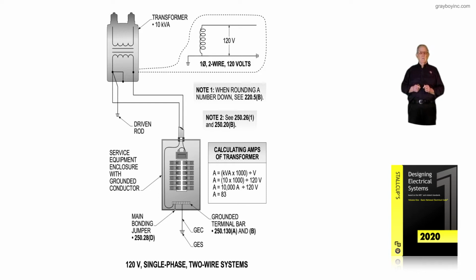And then notice, based upon the number 4 conductor, we would go to our Table 250.66 if we were connecting to a metal water pipe that's good to be used as a grounding electrode, and we could select the size of our grounding electrode conductor from Table 250.66. The grounding electrode system, as just pointed out, we're going to say it's a water pipe. A water pipe that is considered an electrode with 10 feet or more of it in the earth per Section 250.52(A)(1) of the NEC.